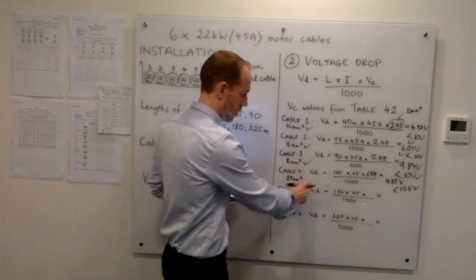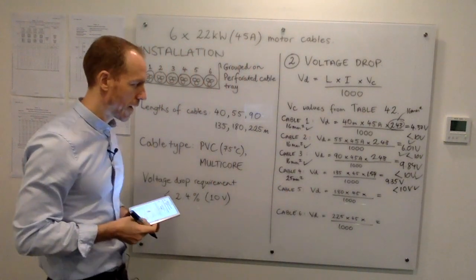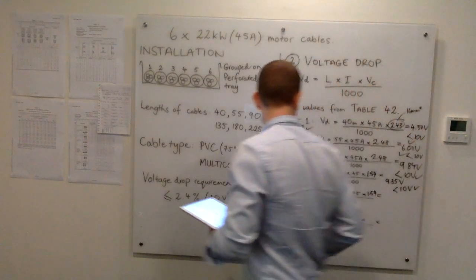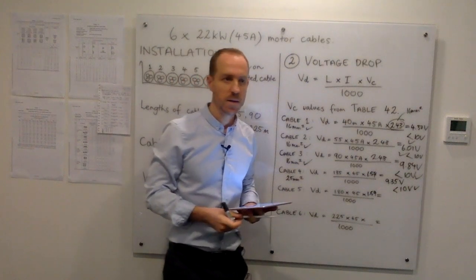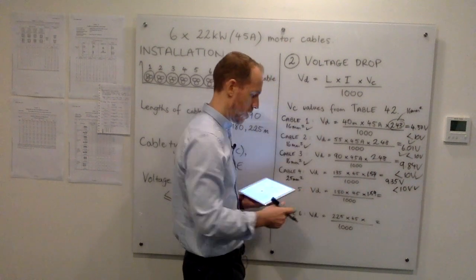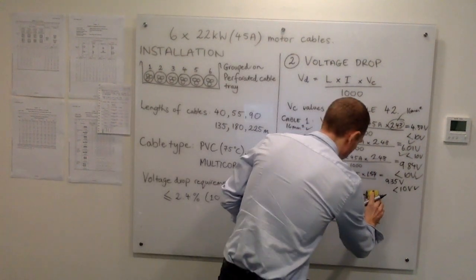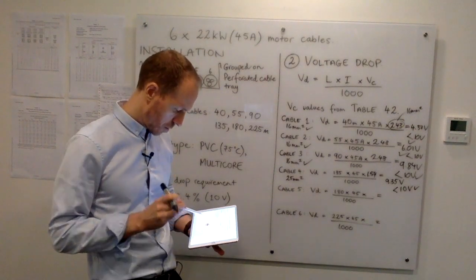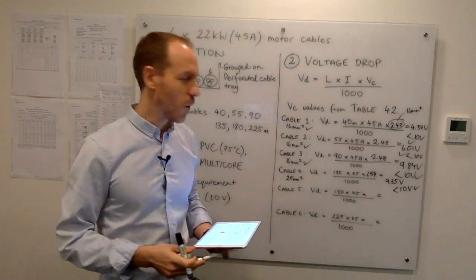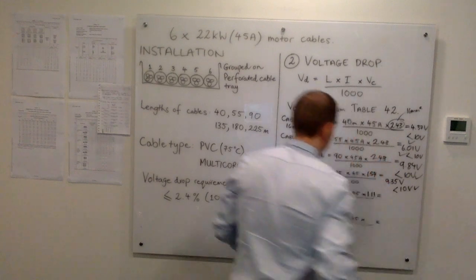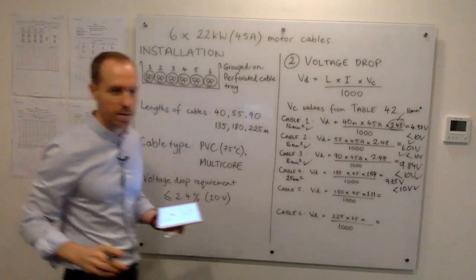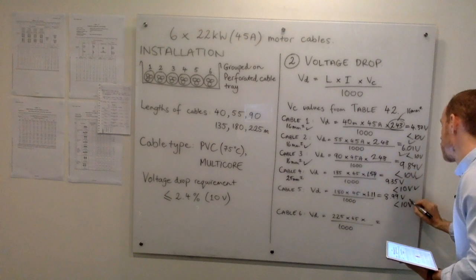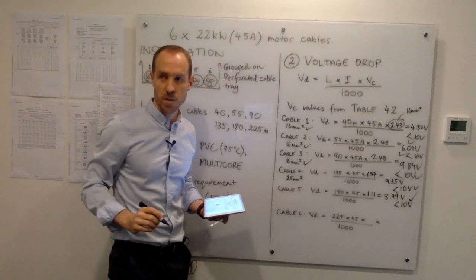Moving on to cable 5 at 180 metres — let's try a 25mm² cable with VC of 1.54. We can see that will be greater than 10 volts, and it is. Therefore, for cable 5 we need to try a 35mm² cable. From table 42, the VC value for 35mm² is 1.11. That works out to be 8.99 volts, which is less than 10 volts. So for cable 5, we need to use at least a 35mm² cable.